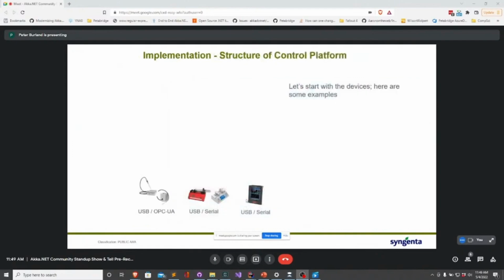So the implementation is obviously huge. This just presents a subset of how we approach this. We have a range of about 20 to 25 devices, all performing different actions. Some we have multiple manufacturers for, some just one. Here we have a heater chiller, where we typically have just one brand. Syringe pumps are cheaper, and we typically have a wider variety of brands, and they have different communications.